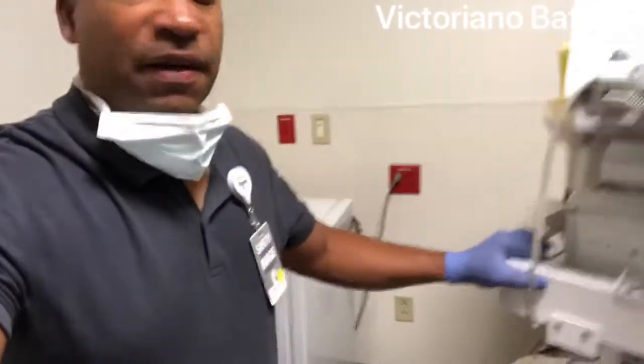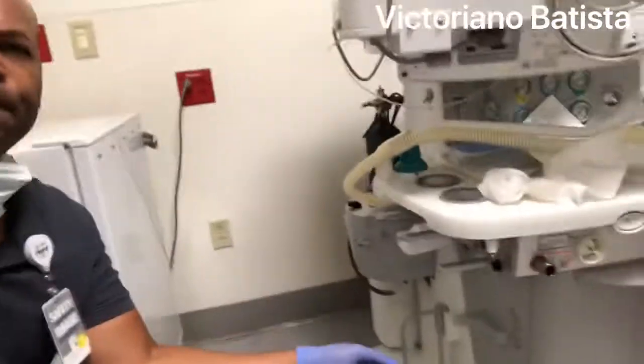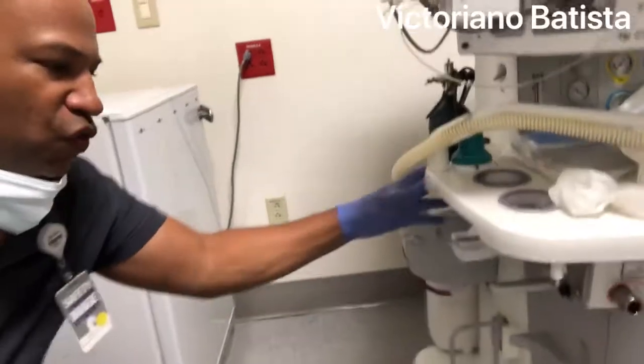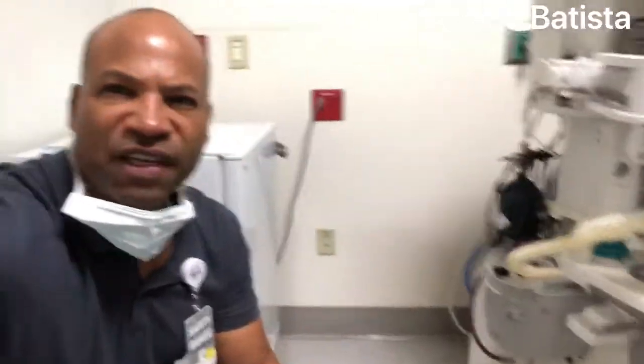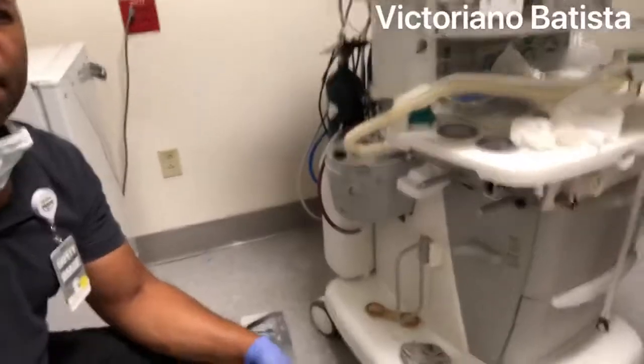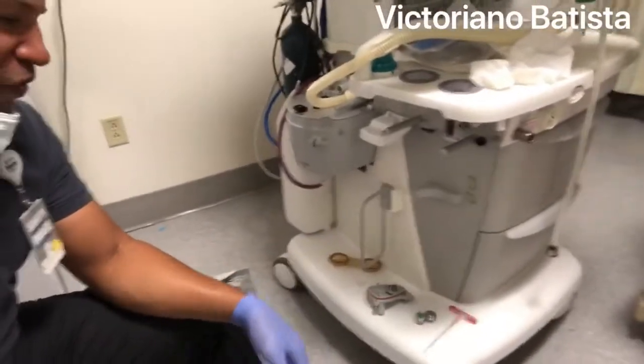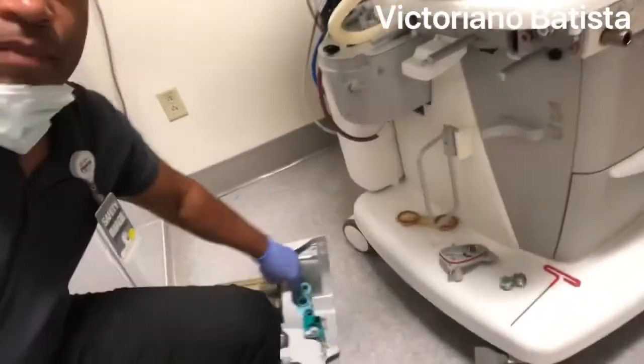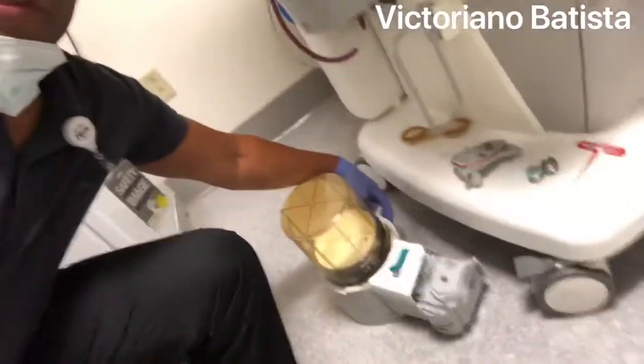Some things that I always find have to do with the area here where you have your pneumatics. This is the area where I find most of the problems are. I think this is just quick tips for maintenance and cleaning out. This can also be done by the operator. Generally, that's what you find in the instruction manual. But it's just basic cleaning procedures when it comes to the breathing system on this unit.